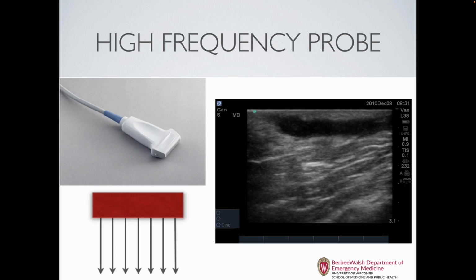So let's talk a little bit about what the individual probes are and what they look like. This first one is the high frequency linear probe. This is the probe that we use pretty commonly for superficial applications like starting an IV or starting a central line for a patient. It has the highest frequency of sound at 10 megahertz. But the trade-off is that the better the picture is, the shallower the depth at which you can get a good and accurate picture. So the high frequency linear probe is only good for a depth of about 6 centimeters, give or take. And this schematic in the lower left-hand corner shows how the crystals are all lined up so that it shoots straight out and comes straight back to the probe and makes a picture that way.